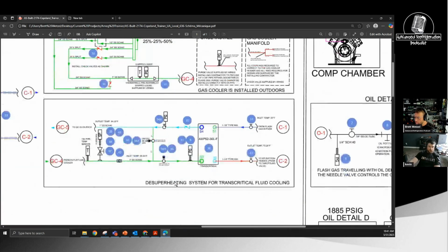If you scroll down -- oh, right here, yep. So we're using kind of like the LMP style subcooler/reheat. This was originally designed to be a subcooler. So when the drop leg, their original set point, I think it was like 95 degrees -- when the drop leg's above 90 to 95 degrees, then they're going to energize the ball valve between the two, and it's going to shut.